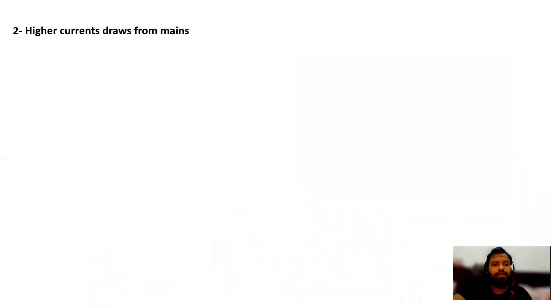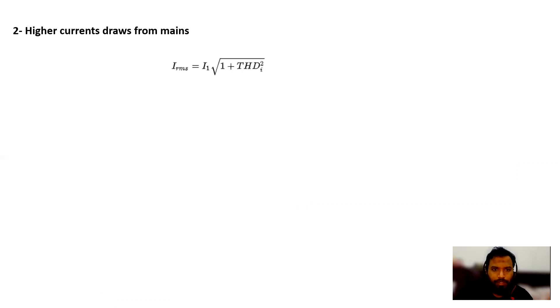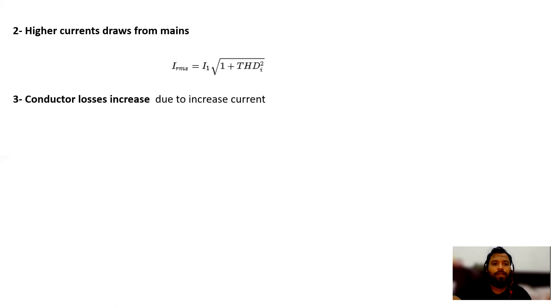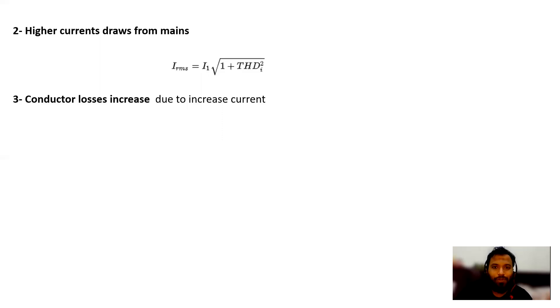The second effect is higher current draw. The RMS formula I explained in an earlier video is: I_rms equals the fundamental current multiplied by the square root of one plus the harmonic current squared. Due to the increase of harmonics the RMS current will be increased, and as a result our conductor losses also increase.